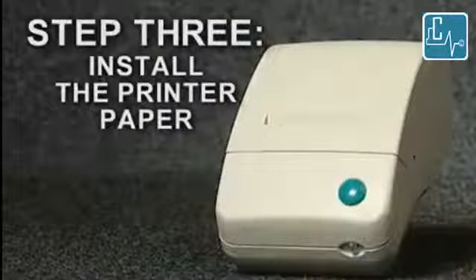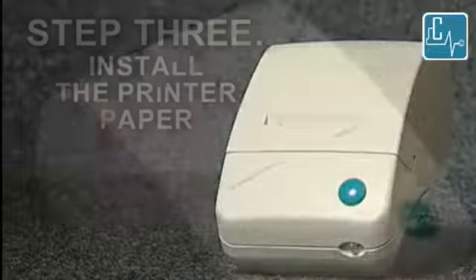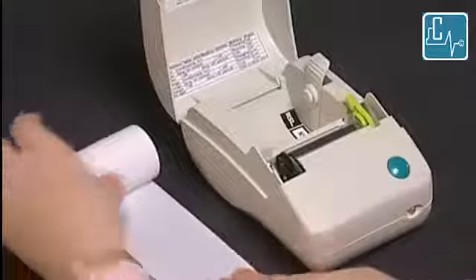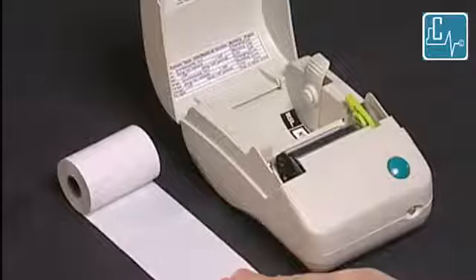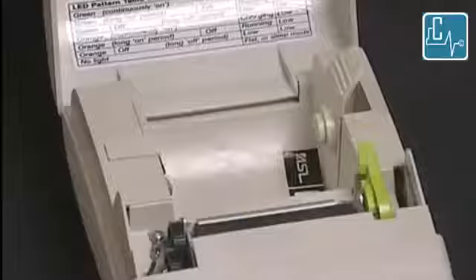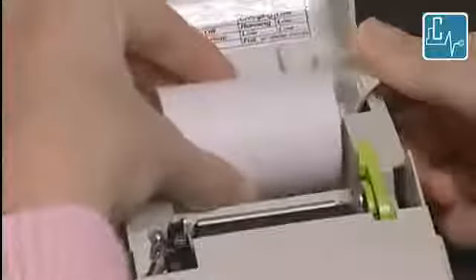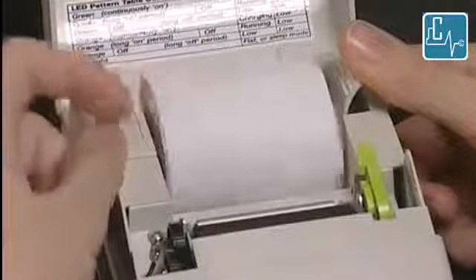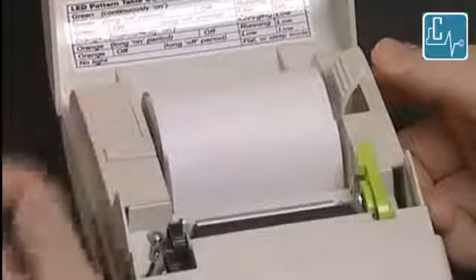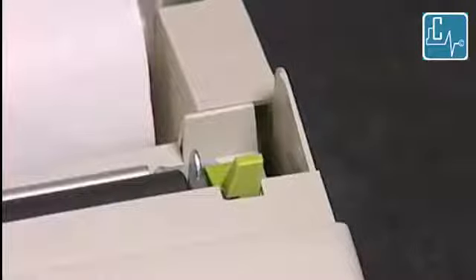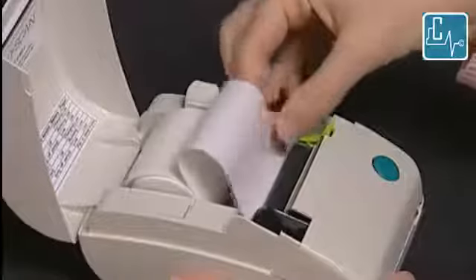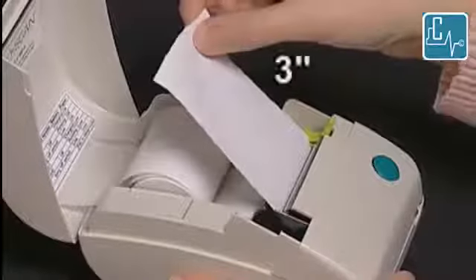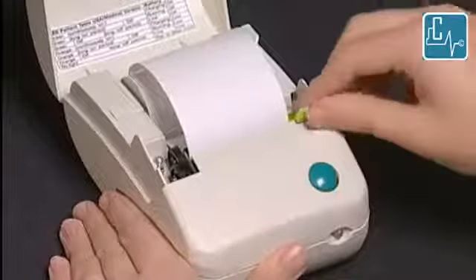In step 3, we will load the thermal paper roll into the printer. First, open the cover on the printer by lifting up and back. Then, place the paper roll next to the printer so that it feeds from the bottom of the roll towards you. Next, move the paper holder lever to the right and place the paper into the printer. Release the lever and make sure the roll turns freely. Now, move the green paper roll release lever towards you until it snaps into the open position. Feed the paper under the black roller until you have approximately 3 inches of paper extending above the black roller. Move the green lever back to its original closed position.